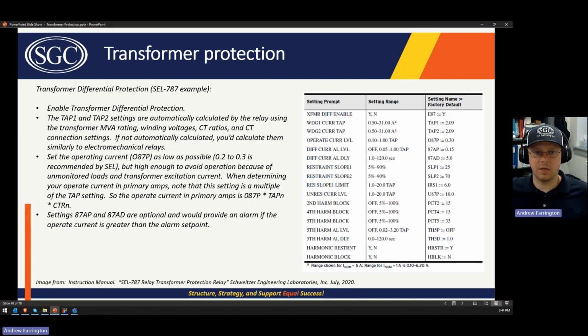If you've set your CT compensation settings incorrectly or your transformer winding configuration settings incorrectly, there will be operate current, and it should be close to the restraint current. And that's a bad sign. And it happens all the time, because you can energize the transformer for that. And for load current, the operate current may be low enough that it doesn't exceed the restraint value on that curve. Okay, so your operate to restraint current isn't above that.